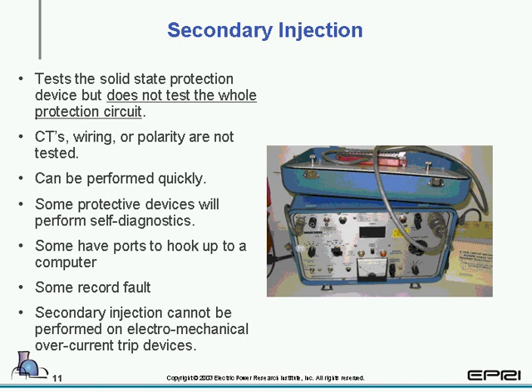Just to clarify, the key difference you have to remember is that primary injection testing will check the CTs, the wiring, and so forth, and of course the overcurrent trip device. Secondary injection testing does not test the CTs or the wiring. It only tests the protective device, the overcurrent trip device. That's why we said earlier that primary current injection is considered a better test: it's more comprehensive.